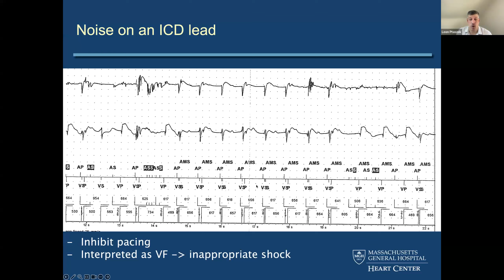But I guess if I had to have one takeaway from this, it would be that if you see noise on either the atrial or the ventricular channel, you need to be investigating what you're going to do about that apparent failure in the conductor. The first course of action is to make sure that it's not due to external electromagnetic interference. Now, sometimes you're seeing these kinds of things on an interrogation for somebody who comes in for just their annual checks for a pacemaker, for example, right? And you're seeing some of these alerts, and then sometimes they'll cluster around certain times. And again, if you're seeing this person in the office, you're not seeing the surface ECGs, right? You're not getting a sense of whether or not this noise occurred due to an external or an internal source.